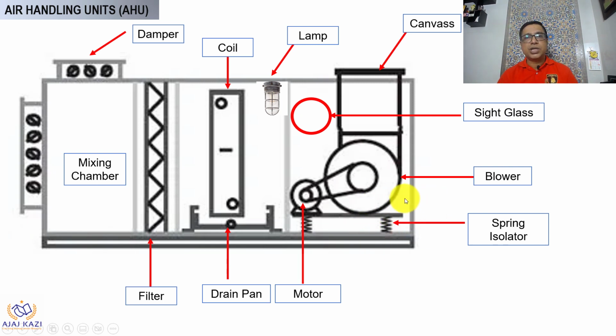Now there are two other things which I have indicated over here. One is called a lamp, which is generally a marine lamp kept inside, because inside is all about water, to see what is happening inside. If it is dark, you can't go with a mobile light and do any maintenance, so it is better for maintenance. The second thing, before you open the door, is a sight glass. This is how the sight glass looks, to see whether the belt is running properly and whether the pulley is coming out, because if you open the door, it might come and hit you. So before you open the door, just see everything is normal, start the light, see everything normal, and then open the door. So these are some of the basic components of air handling units.